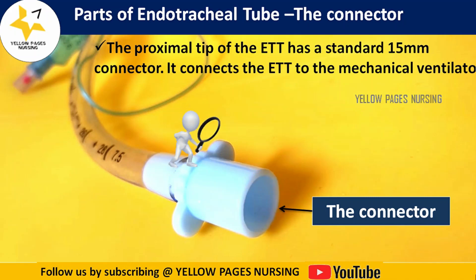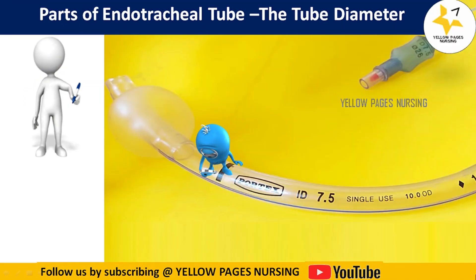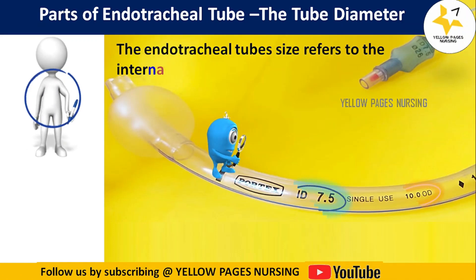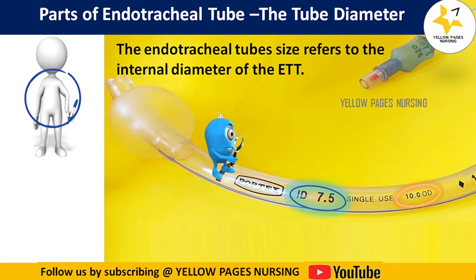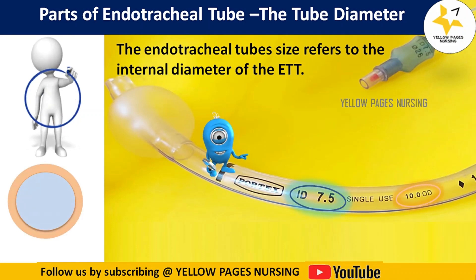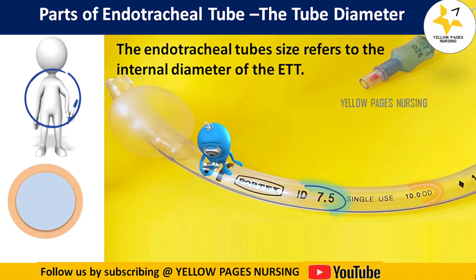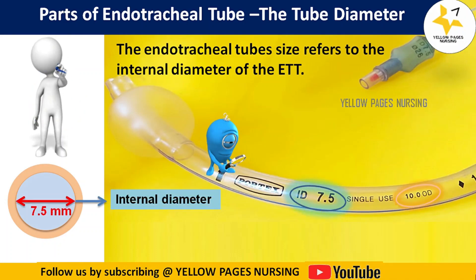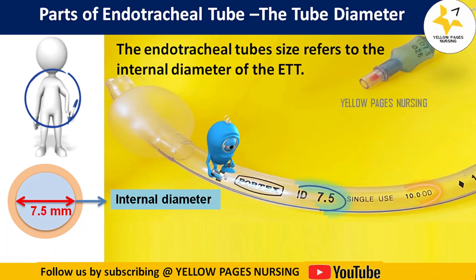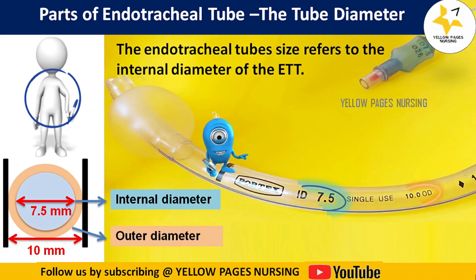Next comes the tube diameter — the endotracheal tube's size refers to the internal diameter of the tube, usually measured in millimeters. From the picture it shows ID 7.5, meaning the internal diameter is 7.5 millimeters, and OD 10, meaning the outer diameter is 10 millimeters. The internal diameter represents the size of the endotracheal tube.